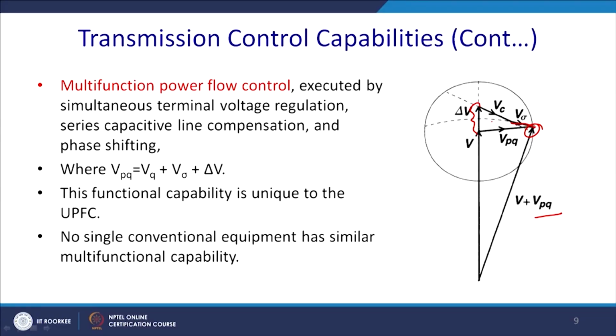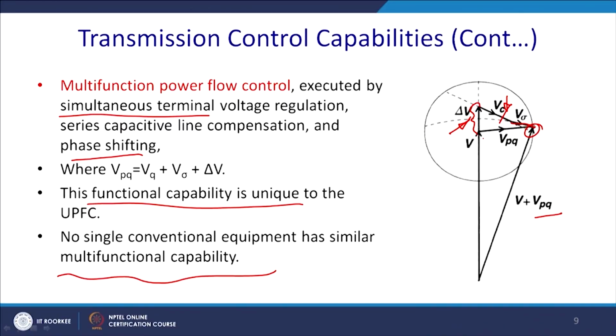Multifunctional power flow control is executed by simultaneous terminal voltage regulation, series capacitance, line compensation, and phase shifting by V sigma, where this functional capability is unique to the UPFC, and mainly you optimize the rating here. No single conventional equipment has similar multifunctional capability. If you wish to achieve it by different FACTS devices, then you require a tap changing transformer for this part, an SSSC for this part, and a PAR, power angle regulator, for this part. So, all those tasks can be combined and successfully executed by the UPFC. That is one of the unique advantages of the UPFC.